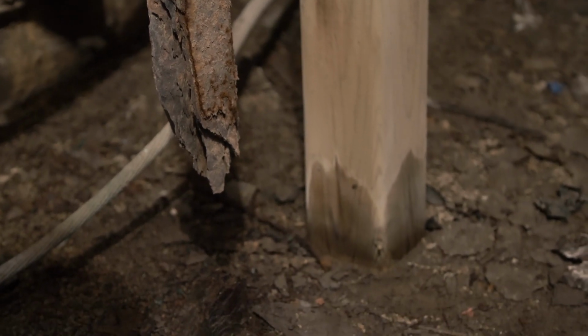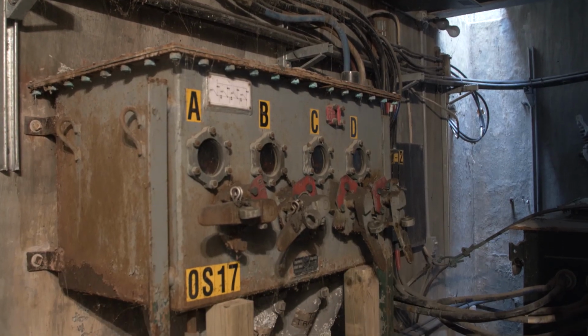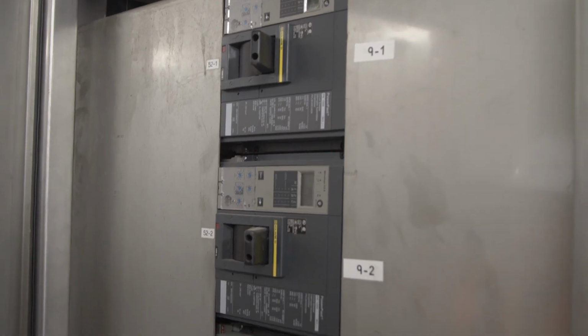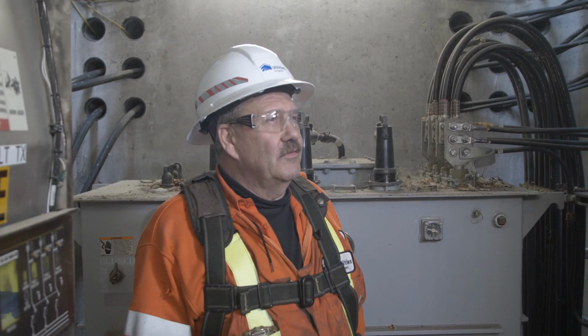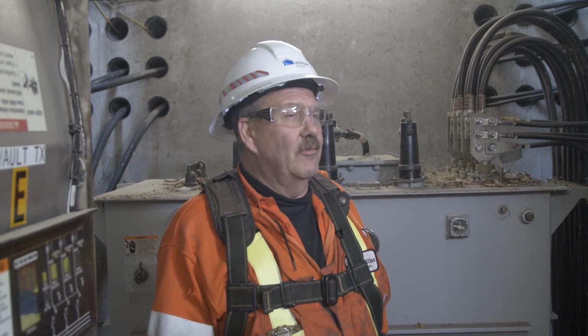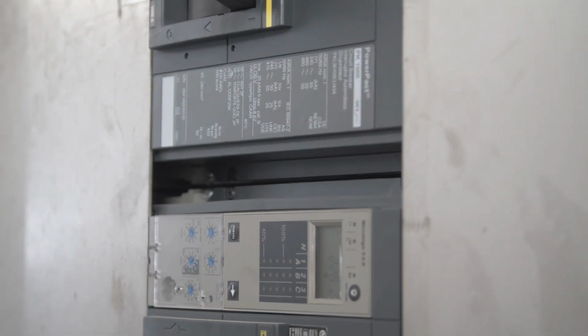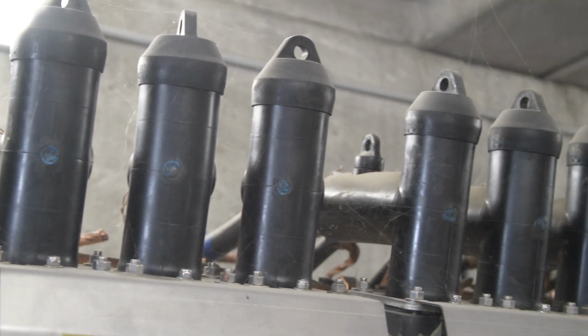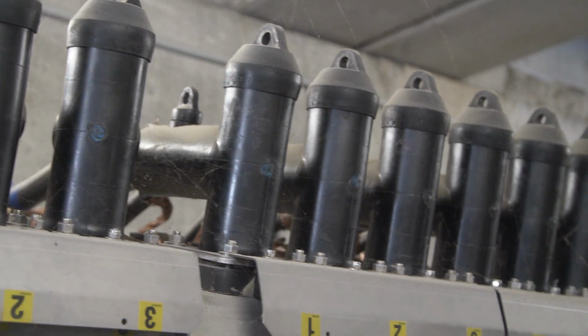One key area of focus in the transformer vaults was the switching equipment, replacing old oil switches with new modern switches. The old vaults with oil switches required outages to operate, which inconvenienced our customers. The new switch replacing our oil switches is a gas switch, and beside me here we can operate these energized.